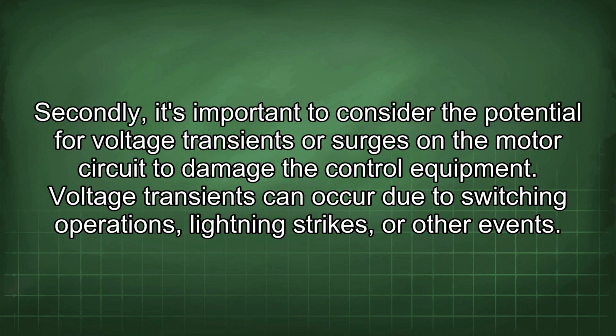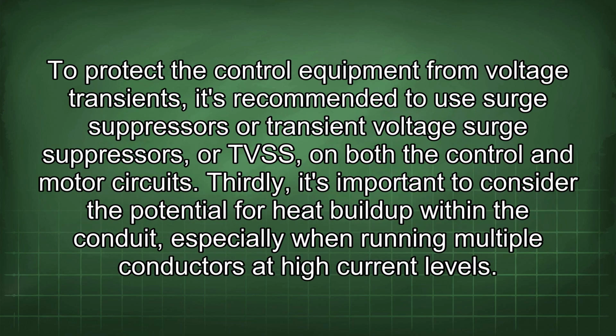Secondly, it's important to consider the potential for voltage transients or surges on the motor circuit to damage the control equipment. Voltage transients can occur due to switching operations, lightning strikes, or other events. To protect the control equipment from voltage transients, it's recommended to use surge suppressors, or transient voltage surge suppressors, or TVSS, on both the control and motor circuits.